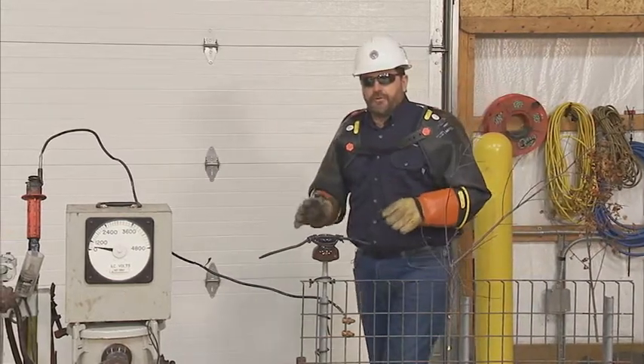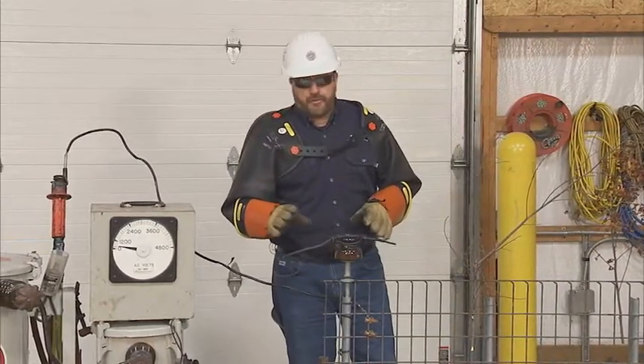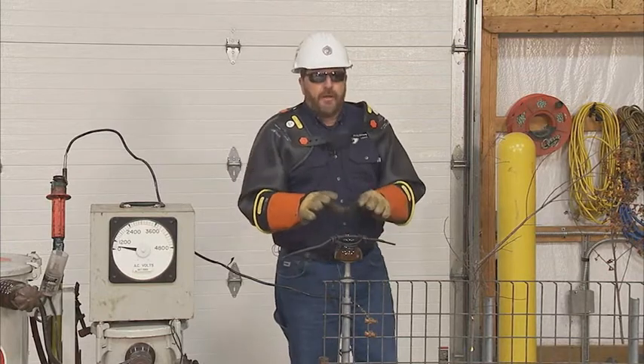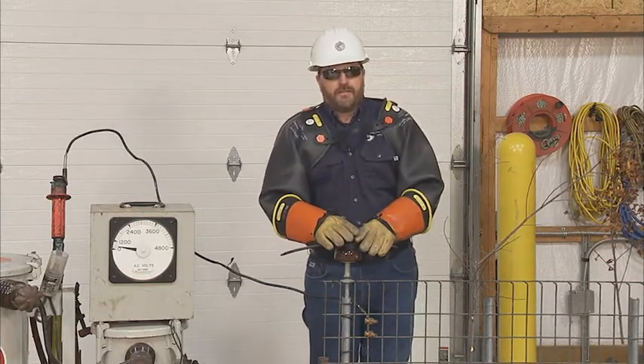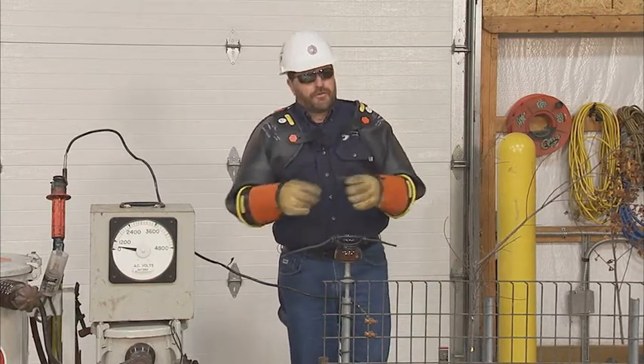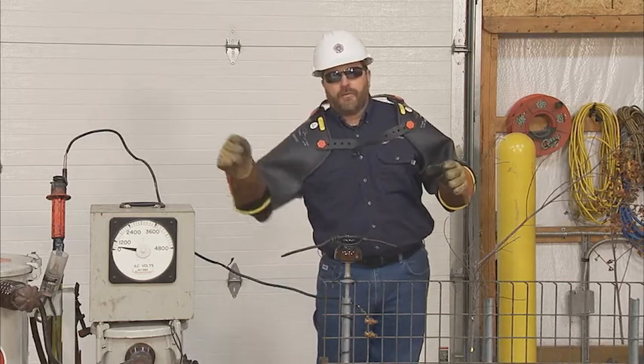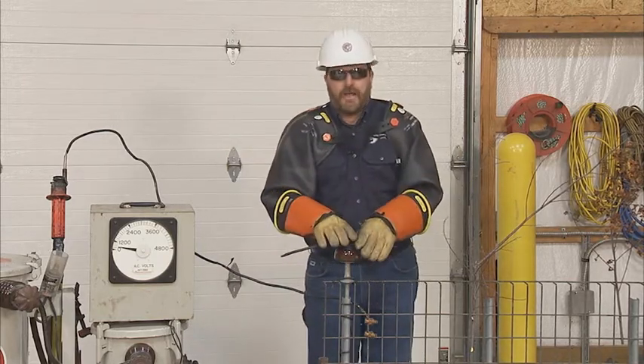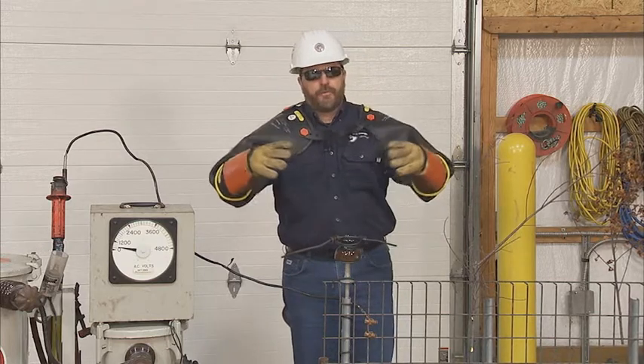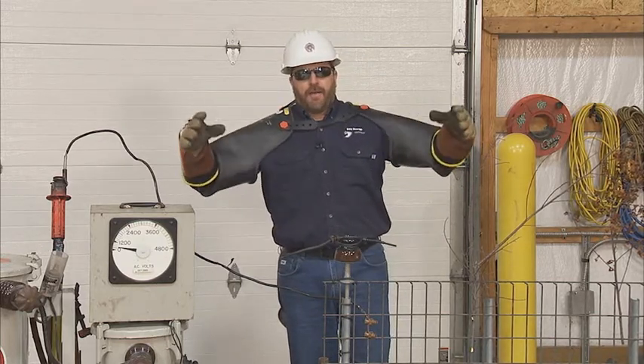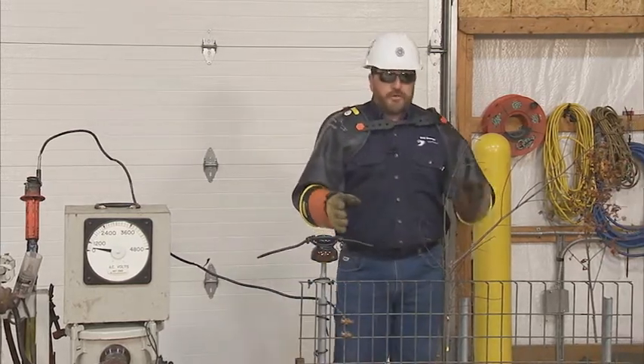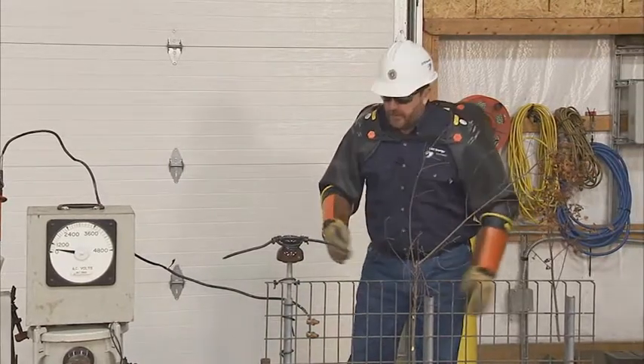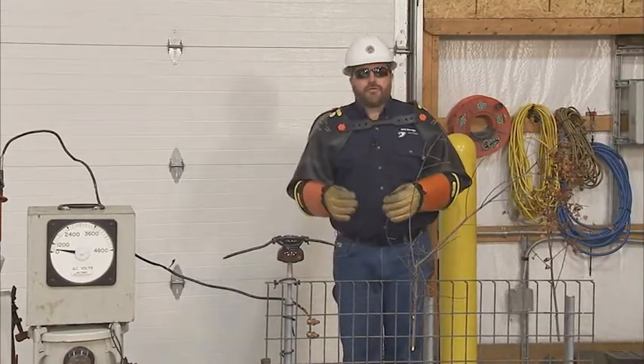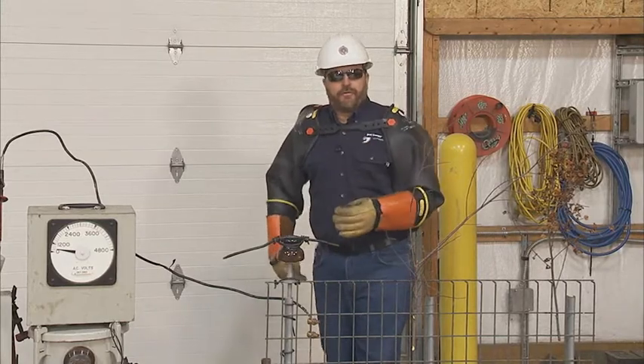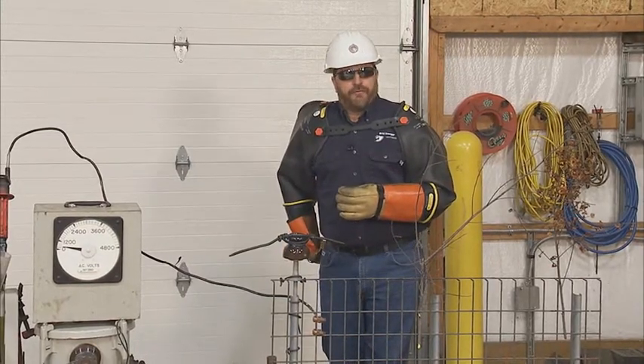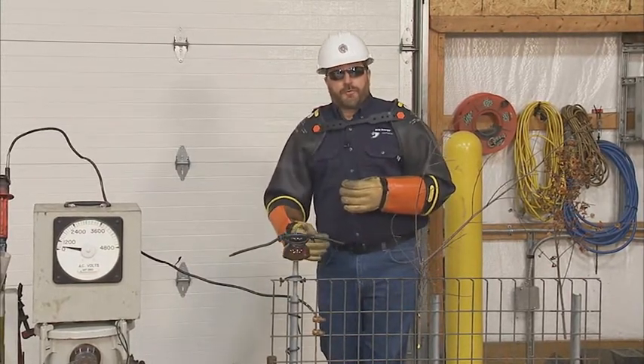What this is similar to is something called step potential. Where that wire's down, a high voltage situation exists. That high voltage situation is like throwing a rock on a pond. When that rock hits the pond, the source of the high voltage is right there. But each ripple outside, as you see on that pond, is a different voltage source, getting to a lower voltage. If you're walking into that step potential situation, from your front foot to your rear foot, what you're going to feel is a difference in the voltage between the two.